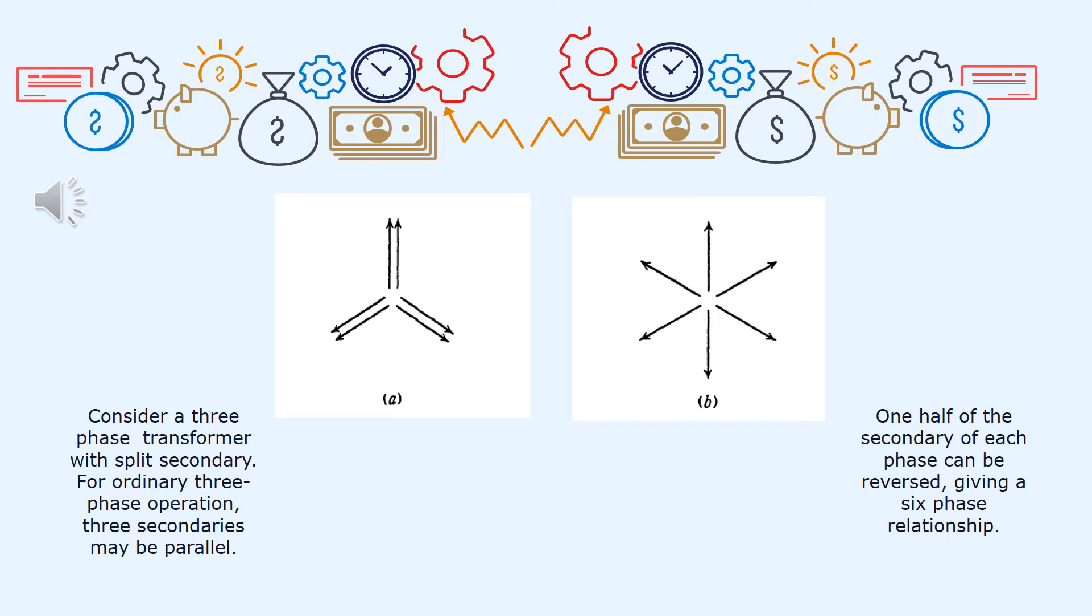Six-phase transformation or connection is also considered as a three-phase transformer or three single-phase transformers with split secondaries. For ordinary three-phase operation, three secondaries may be paralleled as shown in Figure A. On the other hand, one half of the secondary of each phase can be reversed giving a six-phase relationship as shown in Figure B.